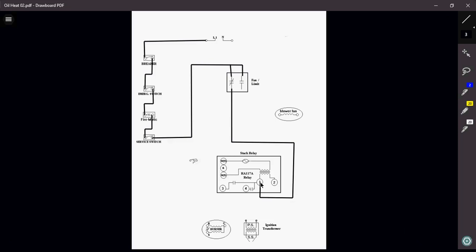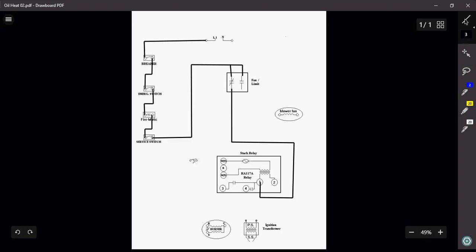So what that's going to do is if this furnace does happen to get overheated, for whatever reason, that's going to open and that will kill my power to my stack relay.